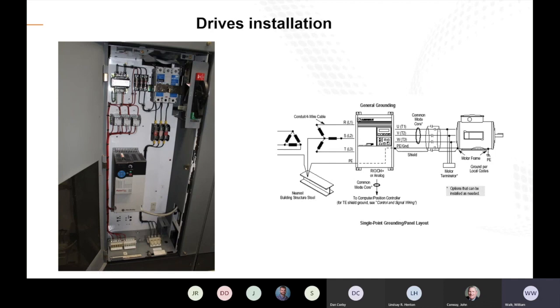So here's a real quick picture of a nice clean installation of the VFD. You can see your protection. We don't have any line reactors because this VFD is installed close to the motor, so we don't suffer any loss or reflected wave from the lead lengths on this. And here on the right is the wiring for that.